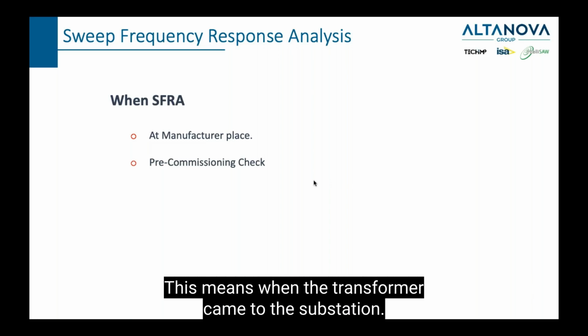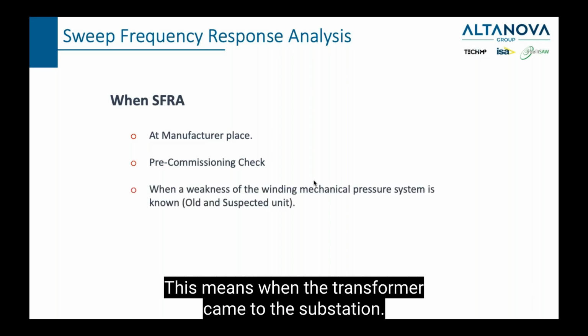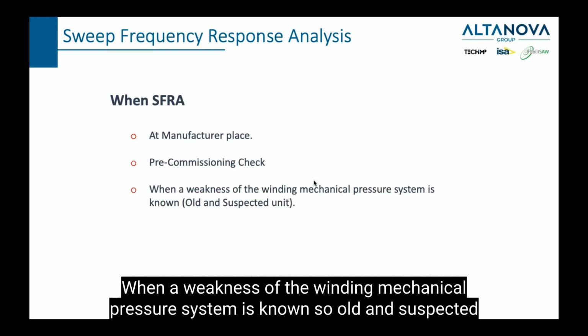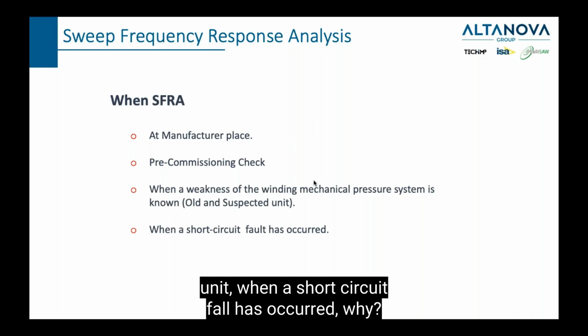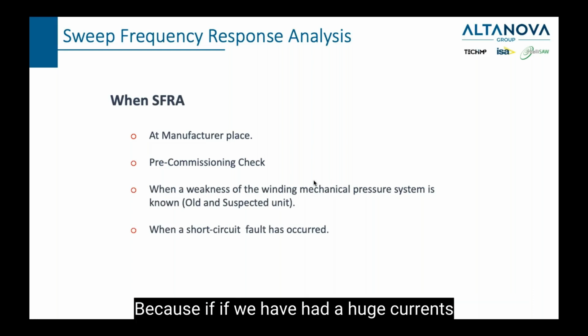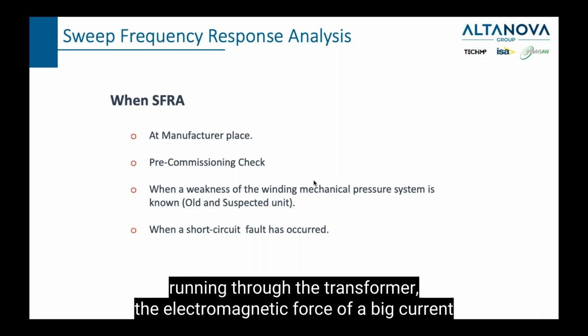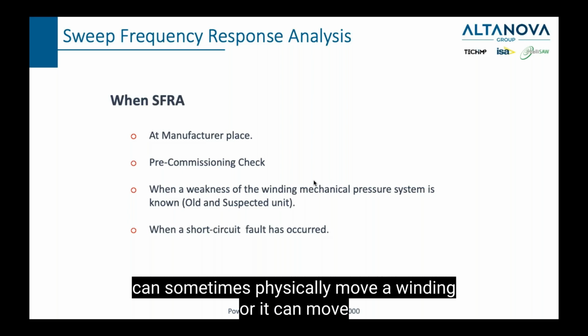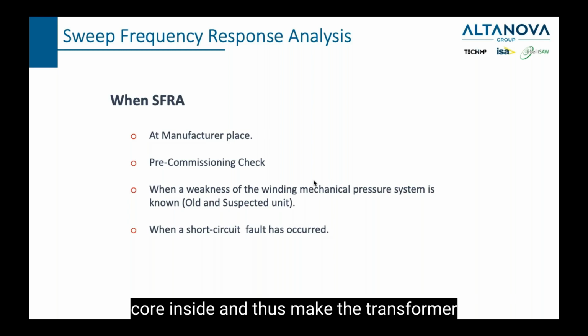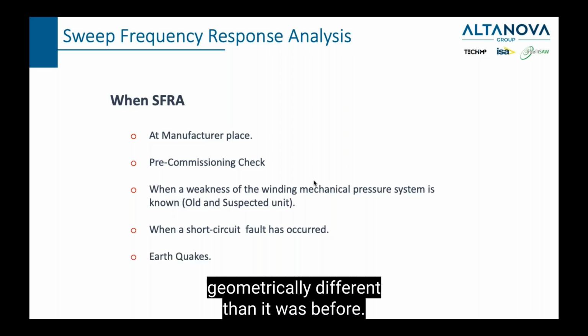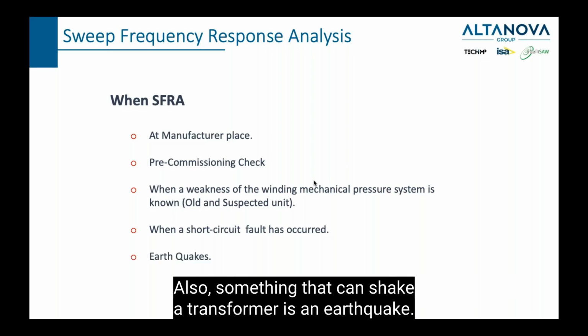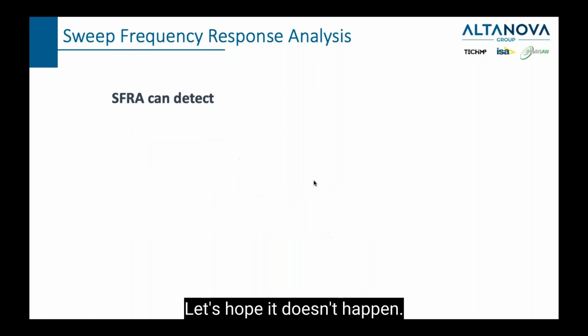This means when the transformer came to the substation. When a weakness of the winding mechanical pressure system is known, so an old and suspected unit, when a short circuit fault has occurred. Why? Because if we have had a huge current running through the transformer, the electromagnetic force of a big current can sometimes physically move a winding, or it can move the core inside and thus make the transformer geometrically different than it was before. Also, something that can shake a transformer is an earthquake. Let's hope it doesn't happen.